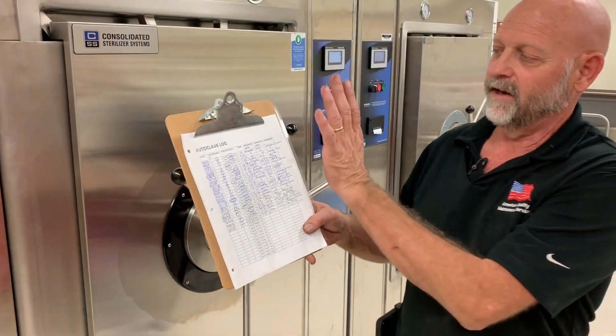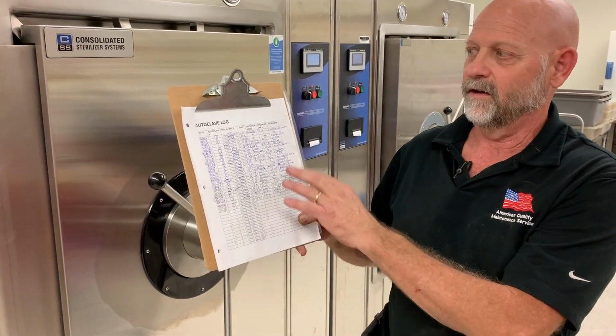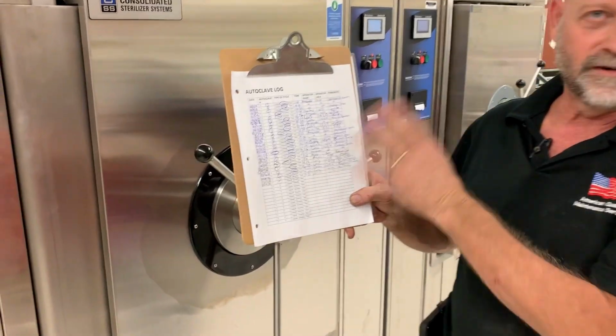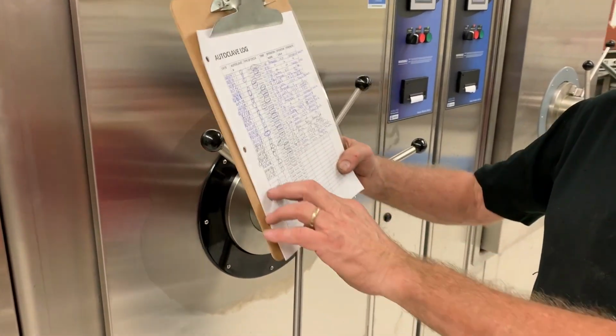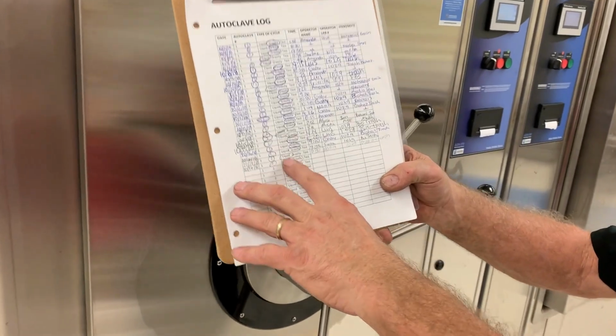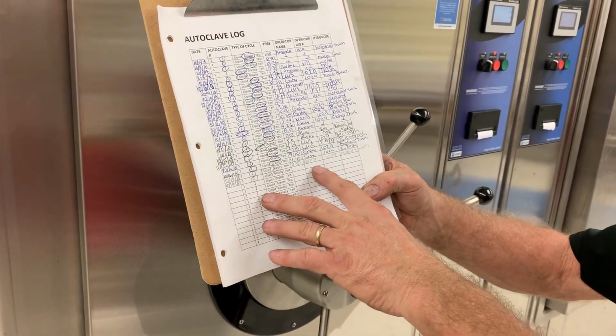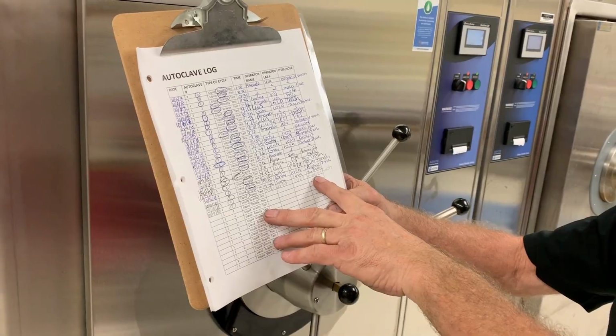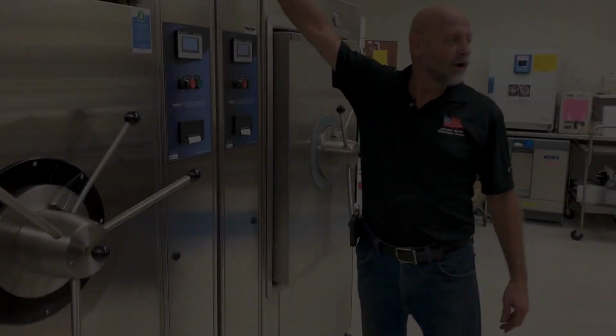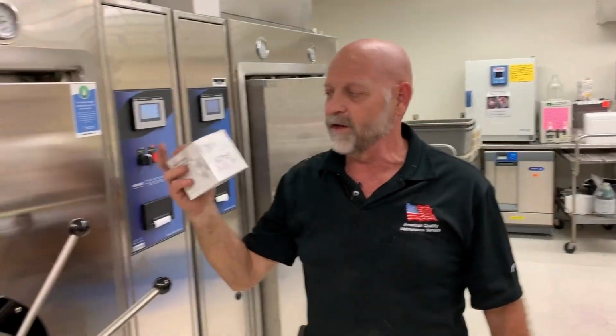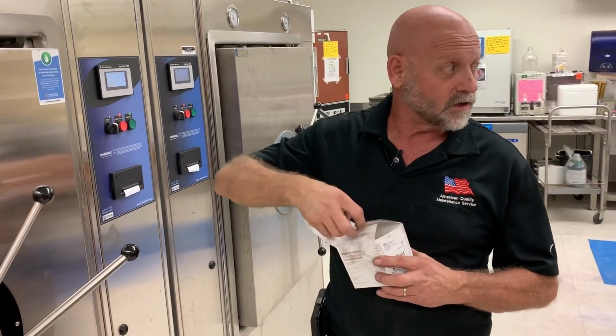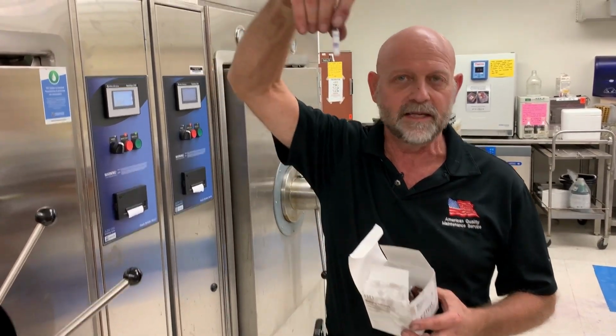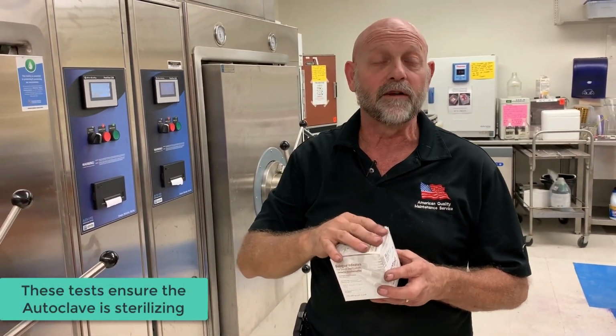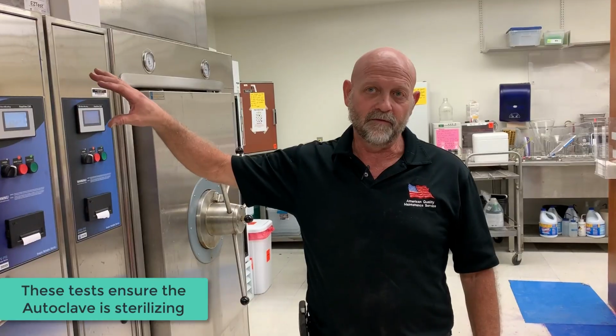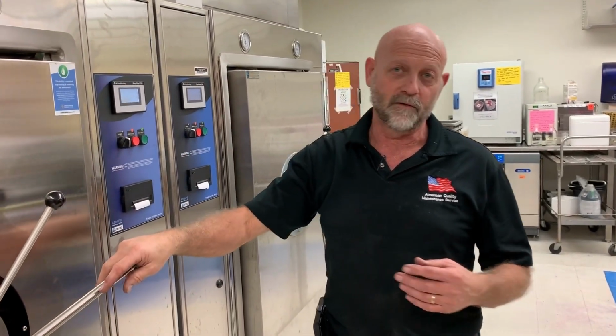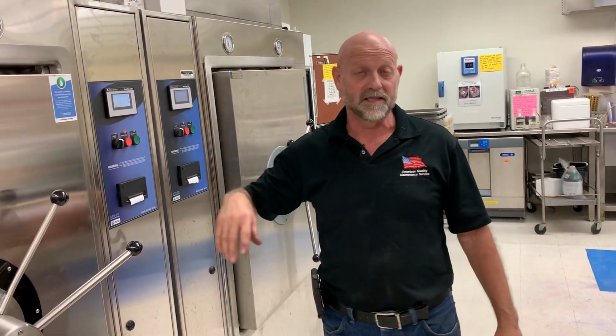Anytime you're running the autoclave, it's imperative that you sign the autoclave log. We need to know every time it's run, it's imperative. We need to know if it's a gravity or a liquid, as you can see. We need to know the time. We need to know the operator and any items or notes. Okay, you also need to do spore tests. The spore tests are done monthly, every 30 days. It needs to run 45 minutes in gravity. If the machine is not sterilizing or can't reach proper pressure, it will abort itself.